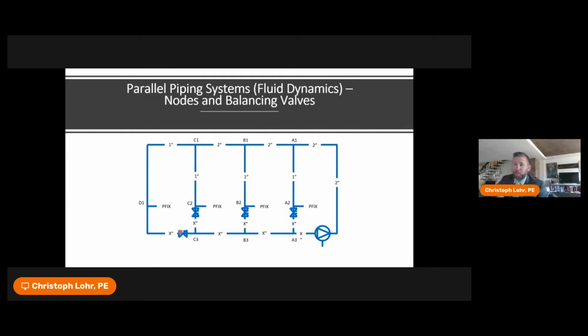Also, sometimes it's hard to determine what the most hydraulically remote loop is. It could be D, but let's say your pipe size in C, instead of being 1 inch, was ½ inch. You'd have to go back and forth and see which one was worse. And then if the contractor installs a system different than what has been shown on the diagrams because of construction conditions, now you've lost controllability. So again, having balancing valves on each one of the loops is generally engineering practice.